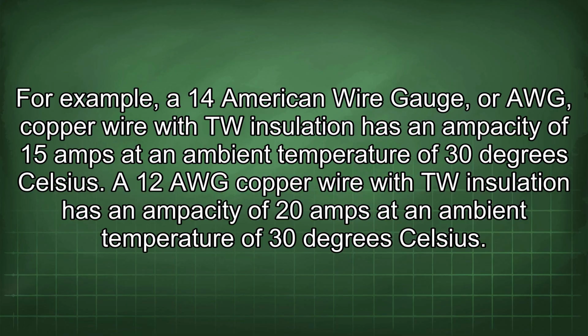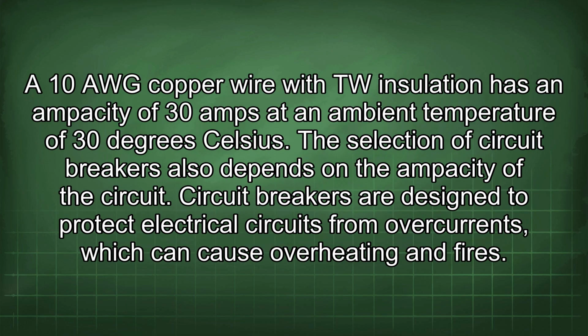A 12 AWG copper wire with TW insulation has an ampacity of 20 amps at an ambient temperature of 30 degrees Celsius. A 10 AWG copper wire with TW insulation has an ampacity of 30 amps at an ambient temperature of 30 degrees Celsius. The selection of circuit breakers also depends on the ampacity of the circuit.